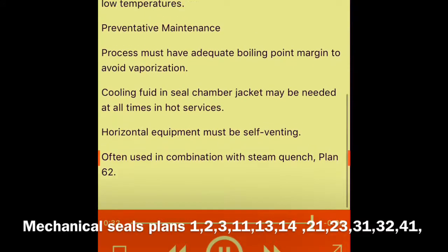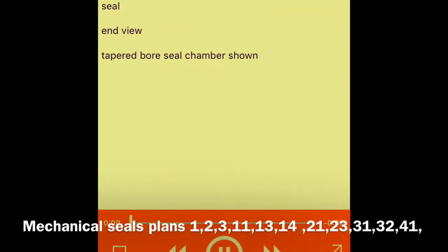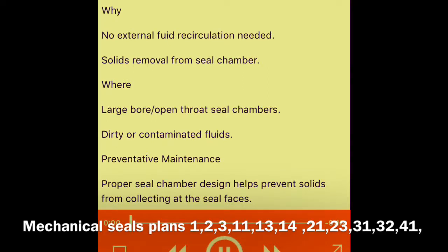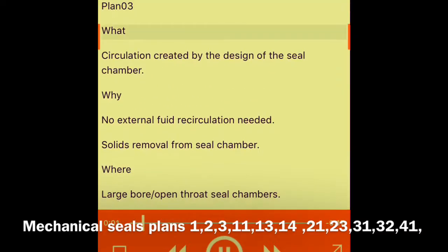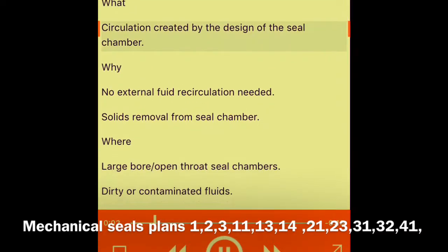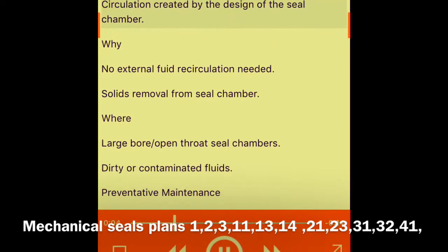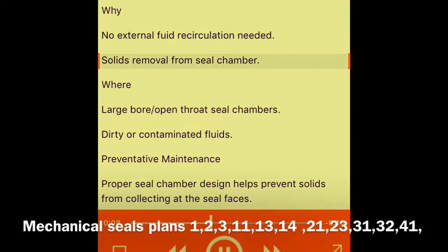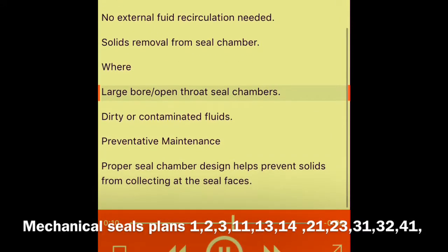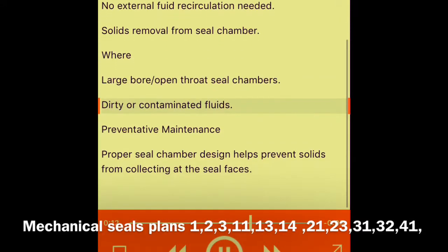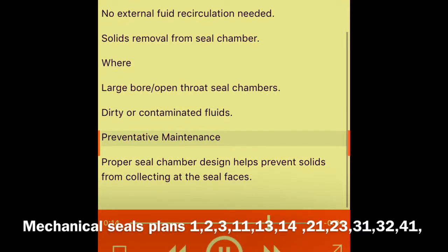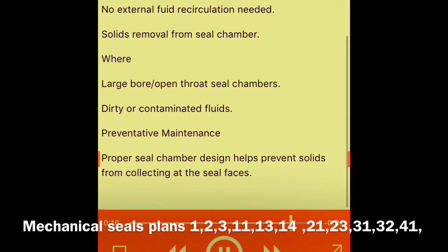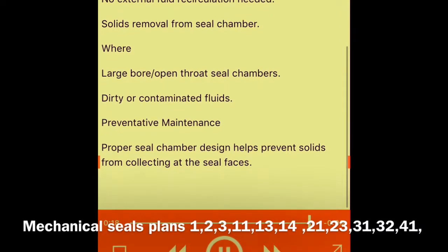Plan 03 — seal end view, tapered bore seal chamber shown. What: circulation created by the design of the seal chamber. Why: no external fluid recirculation needed; solids removal from seal chamber. Where: large or open throat seal chambers; dirty or contaminated fluids. Preventative maintenance: proper seal chamber design helps prevent solids from collecting at the seal faces.